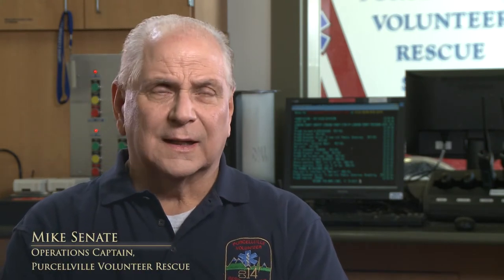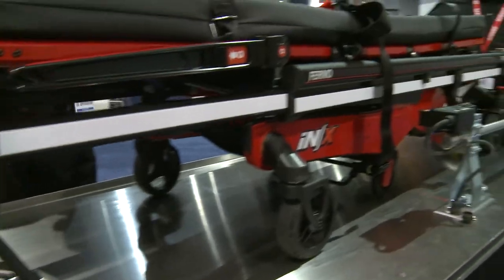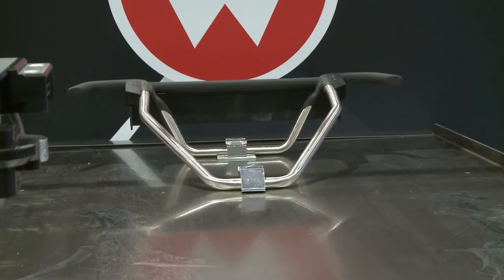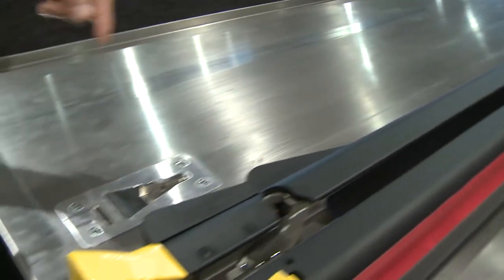It's really important to the safety of the patient that the cot be held to the floor 100%. The industry standard has used an antler-and-rail style system to affix the cot to the ambulance floor for many years. That was done because it's very easy to use and there's a lot of familiarity with it over the last few decades. The litter manufacturers have now migrated to a new track method of restraint.